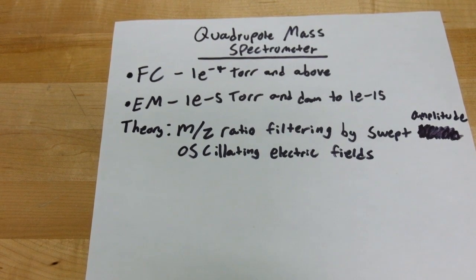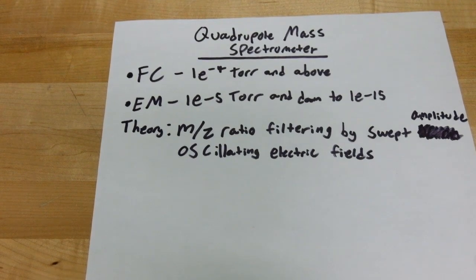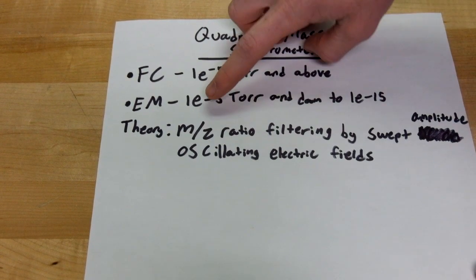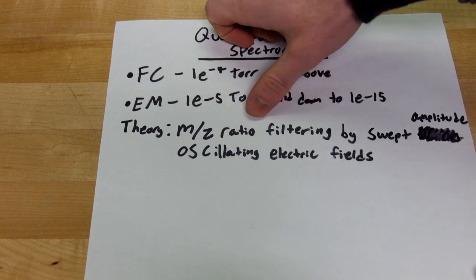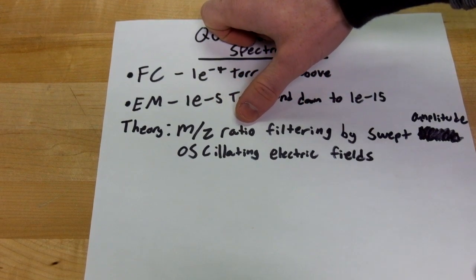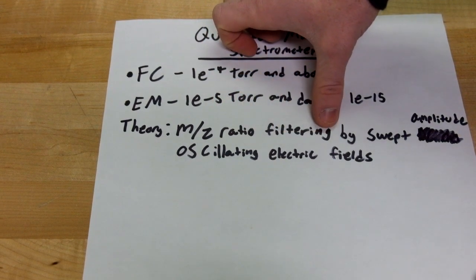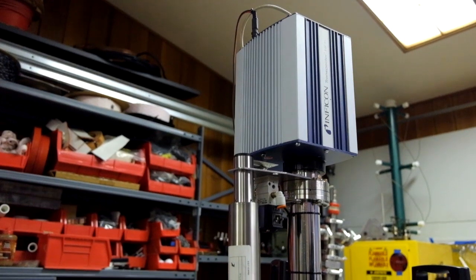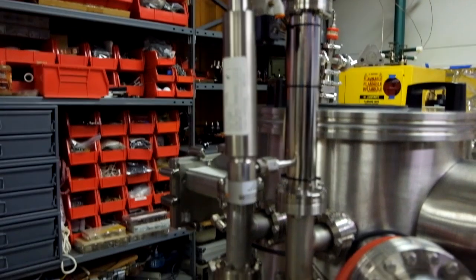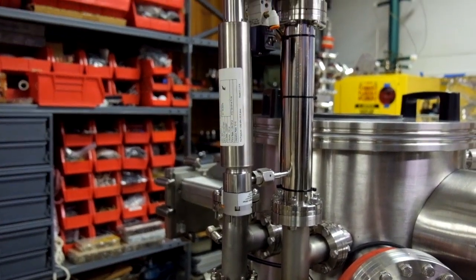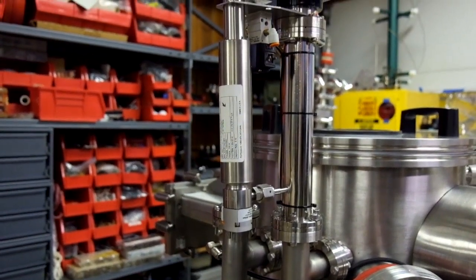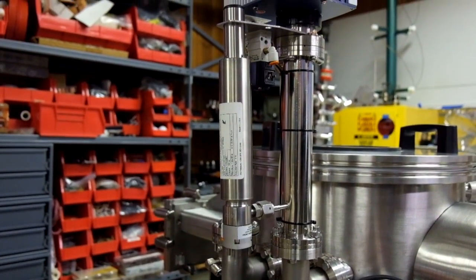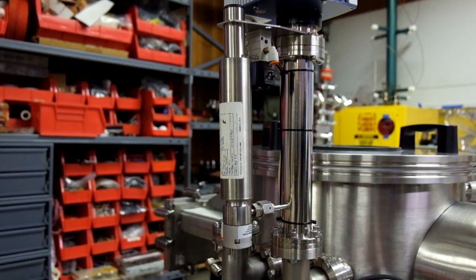I'll go over what's actually inside of it in a second, but basically what it does is separate ions by their mass-to-charge ratio by sweeping an electric field in the analyzer region of the device. Before I had this, the extent of my vacuum diagnostics were basically looking at a couple of vacuum gauges and saying it looks good enough — but that really doesn't tell you even a part of the whole picture.